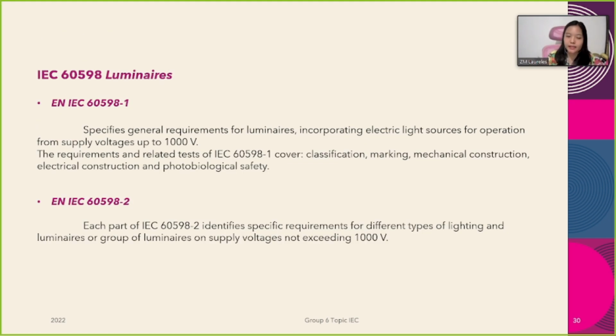Next, for the IEC 60598, yung luminaires naman natin. So, 60598-1 specifies general requirements for luminaires, incorporating electrical light sources for operation from supply voltages up to 1,000 volts. So, yung requirements na to and yung mga related test of IEC 60598-1, ang kino-cover niya is yung classification, marking, mechanical construction, electrical construction, and then yung photobiological safety.